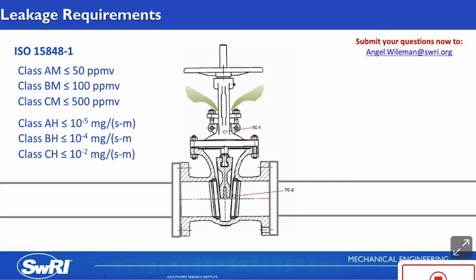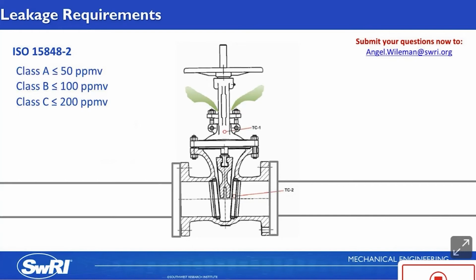Again, there are three classes depending on the measured rate, with AH being 10 to the negative 5 milligrams per second per meter, and CH 10 to the negative 2 milligrams per second per meter. The stem seal leakage requirements in ISO 15848-2 are also broken up into three tightness classes, but these are defined as a concentration, ranging from 50 parts per million by volume for Class A to 200 parts per million by volume for Class C.